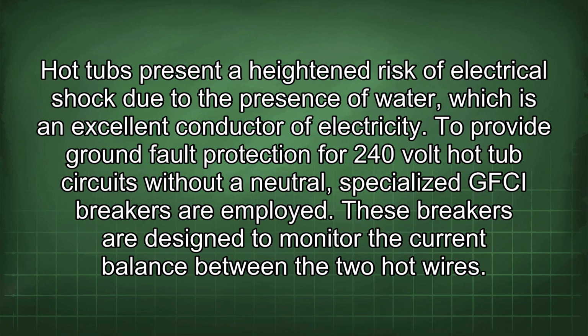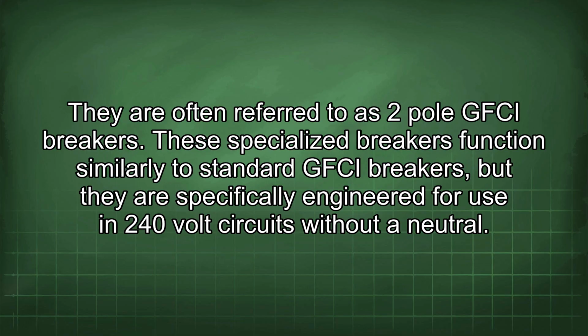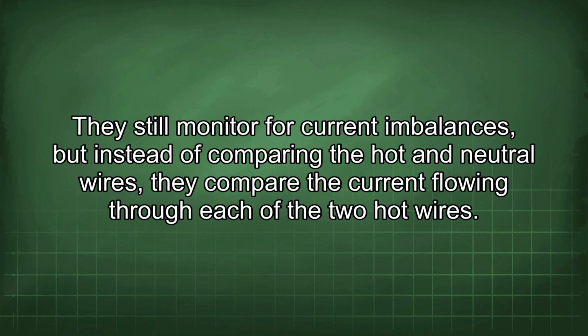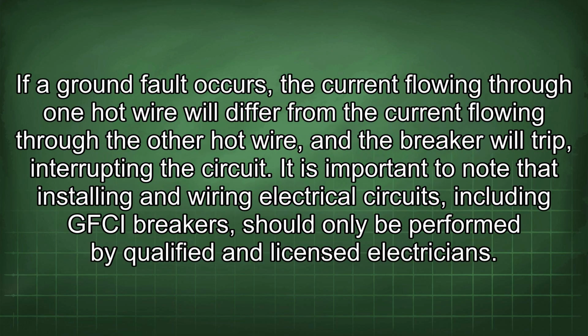To provide ground fault protection for 240-volt hot tub circuits without a neutral, specialized GFCI breakers are employed. These breakers are designed to monitor the current balance between the two hot wires. They are often referred to as two-pole GFCI breakers. These specialized breakers function similarly to standard GFCI breakers, but they are specifically engineered for use in 240-volt circuits without a neutral. They still monitor for current imbalances, but instead of comparing the hot and neutral wires, they compare the current flowing through each of the two hot wires. If a ground fault occurs, the current flowing through one hot wire will differ from the current flowing through the other hot wire, and the breaker will trip, interrupting the circuit.